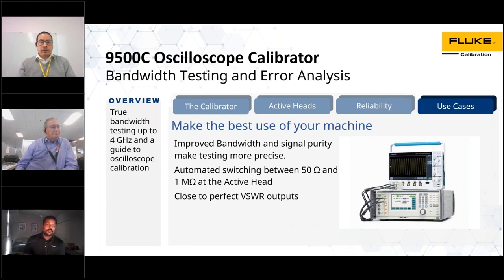Lastly, to make the best use of your machine, we have improved bandwidth and signal purity, making the testing a lot more precise. I've already spoken about the automated switching between the 50 ohm and megohm impedance, and it's done at the active head without any additional equipment. And we're seeing close to perfect VSWR outputs. We're seeing less than 1.1 up to 550 megahertz, less than 1.2 between 550 megahertz and 3 gigahertz, and less than 1.3 up to 4 gigahertz. The true bandwidth testing up to 4 gigahertz can really improve the capabilities of your calibration lab with the 9540C heads and the 9500C oscilloscope calibrator.